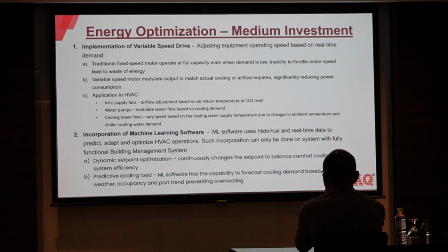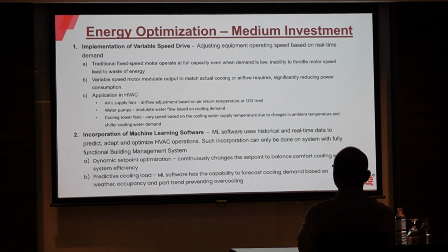Because in a lot of cases during the design stage, we will design the equipment to meet the peak of peak. But the peak will only happen maybe 1 or 2% during the year. Most of the time it is operating at part load. So with this VSD, we can basically throttle the speed until it gives the actual required cooling.